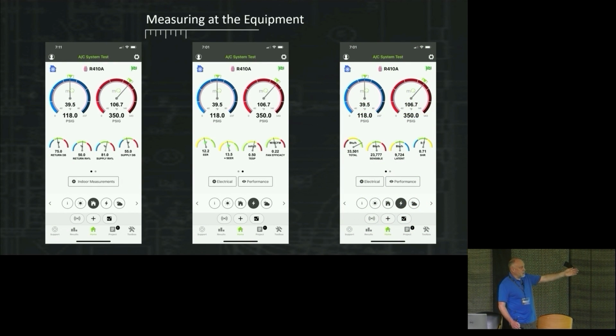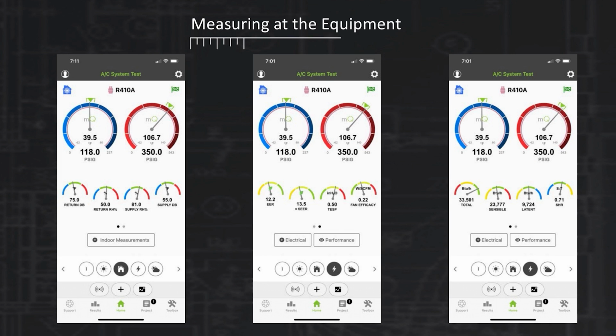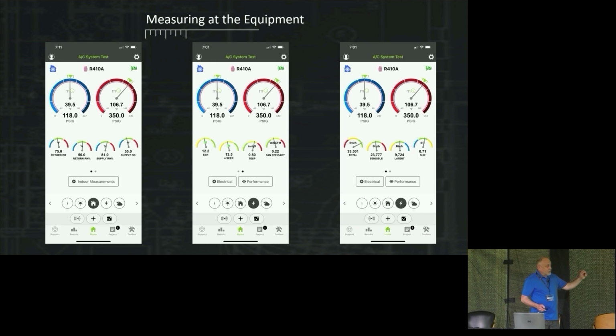And just to show you a difference here, I've got a system here. It's got 75-degree return air. It's running about 13.5 SEER, I believe, and we're running like 33,000 BTUs. I'm semi-blind up here, so I think those numbers are right. So about 33,500 BTUs. I'm literally going to just take a probe and move it from the equipment. So this is testing at the equipment, right? The equipment's working great.